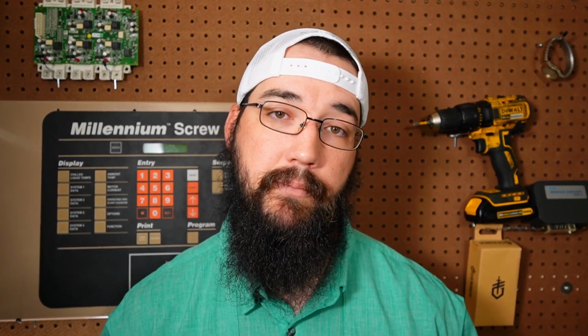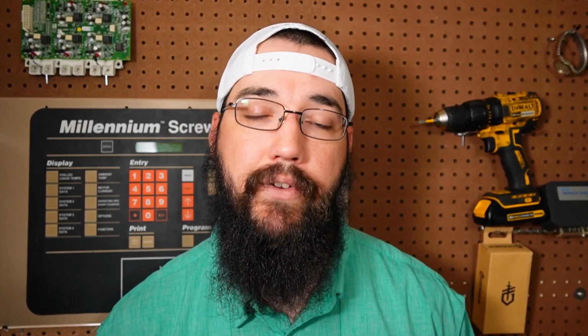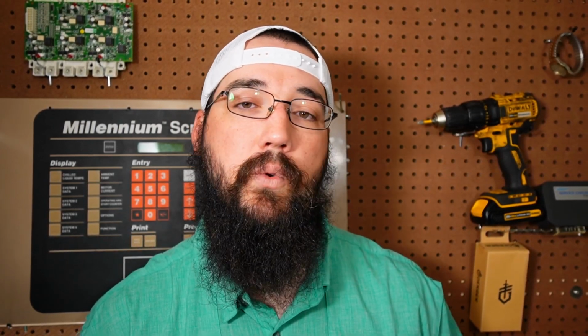Okay, so you've gone through all this process, all these little details, you've looked at this whole thing. Heck, you've been monitoring this system for 3 or 4 days, changing oil, going through the whole process maybe, and you finally hit 500 microns, or you dip below it, say 450, 400, something like that. You really get a great pull. Then you isolate and it doesn't really move that much. Fantastic. I have seen practices where all the technician is looking for is 20, 30 minutes, an hour, and then they want to call the evacuation good, start throwing charge in there and move on.